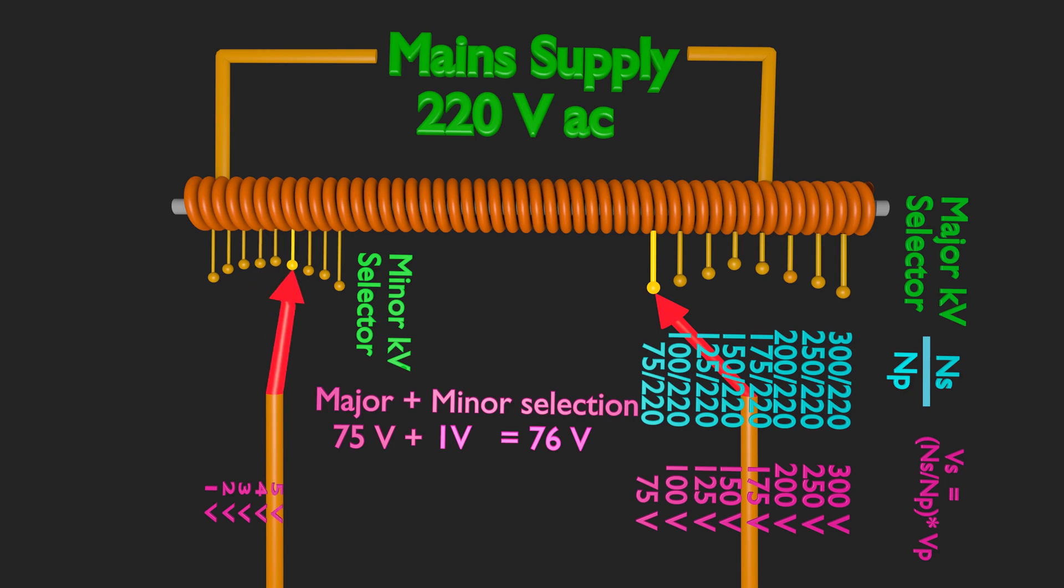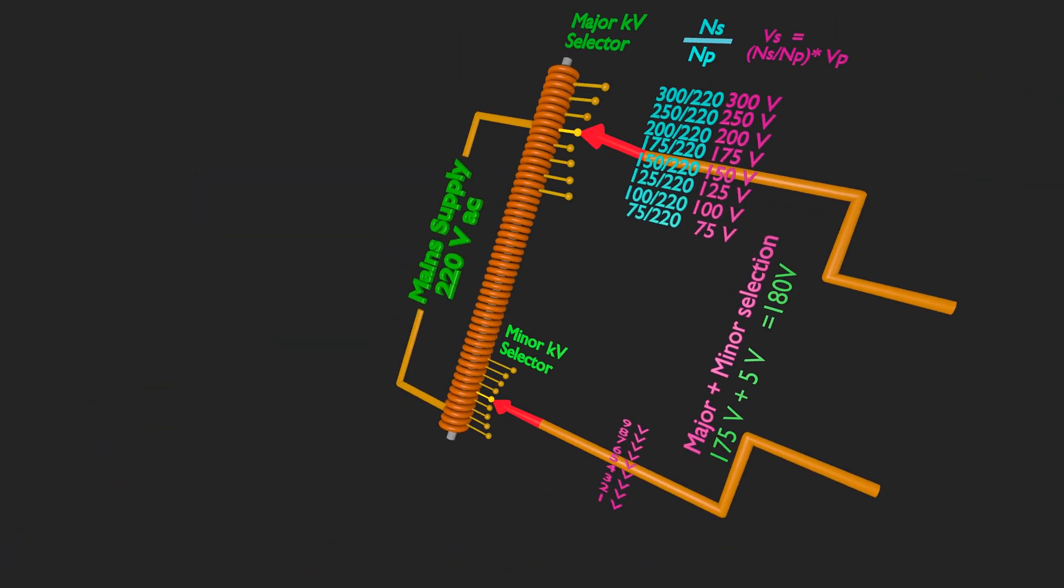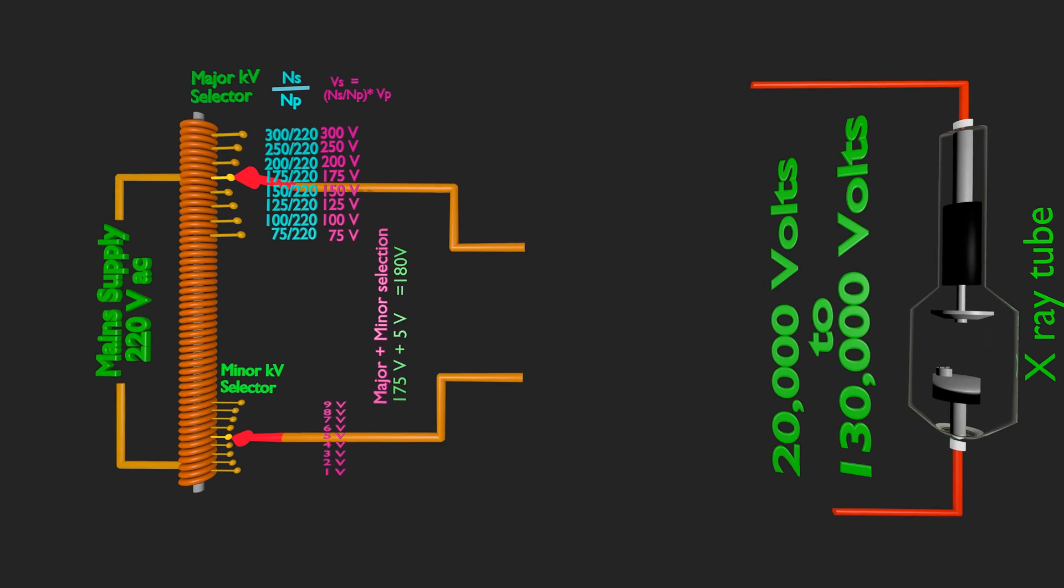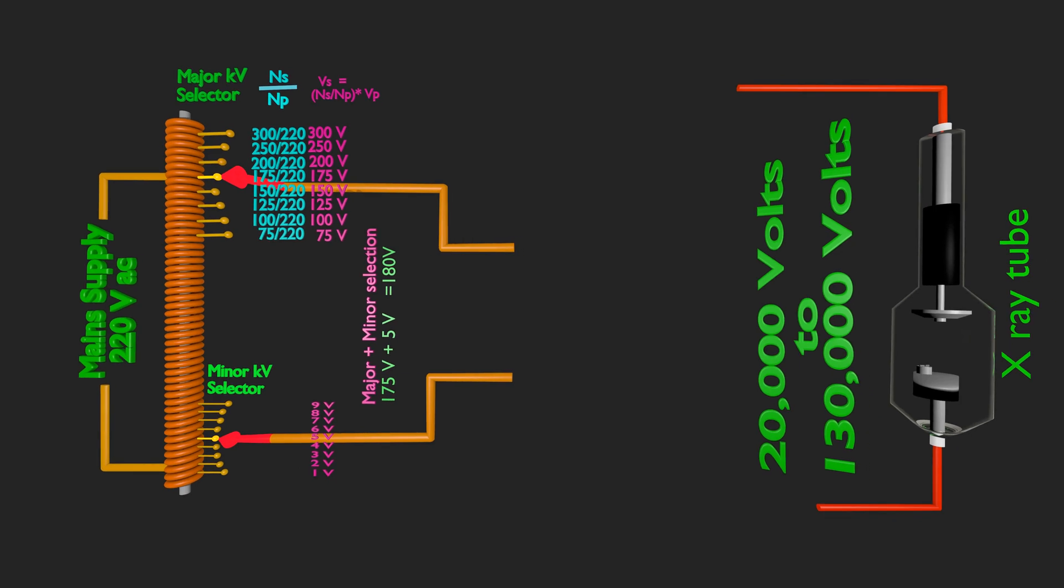As we shift from one tapping to other, voltages can be available at an increment of 1 volt. Let's fix our voltage across secondary at 180 volt, with 5 volt minor and 175 volt major tapping. This voltage of 180 volt has to be increased to kilovoltage range before applying to X-ray tube. This transformation is achieved by a step-up transformer.